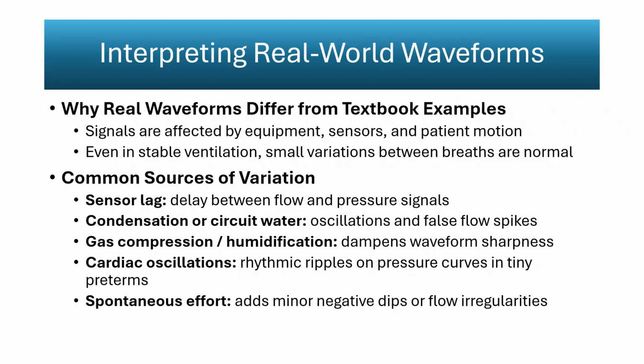Gas compression and humidification also soften waveform edges. Because part of the delivered volume goes into compressing the circuit and warming humidified gas, pressure and flow tracings lose some of their sharpness compared with textbook loops. In tiny preterm infants, cardiac oscillations may be visible as small rhythmic ripples on the pressure curve. The proximity of the heart to the compliant chest wall allows each heartbeat to transmit pressure pulses into the airway, creating subtle, repeating deflections that are physiologic rather than pathologic.